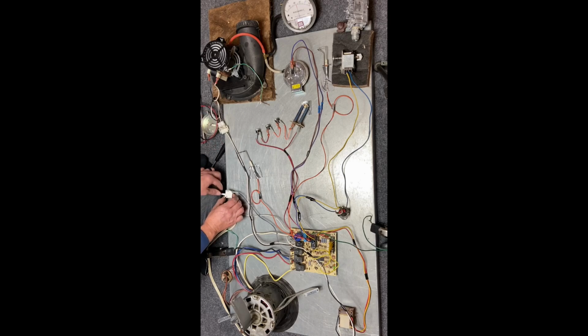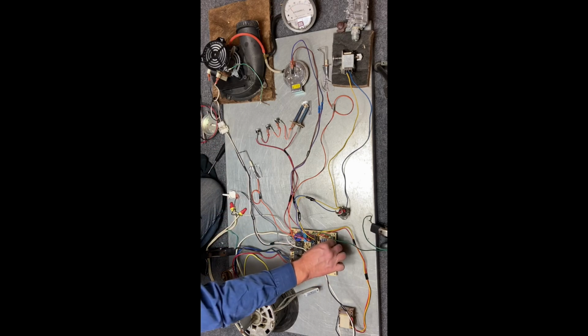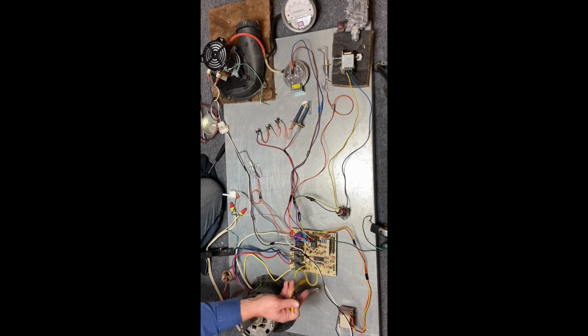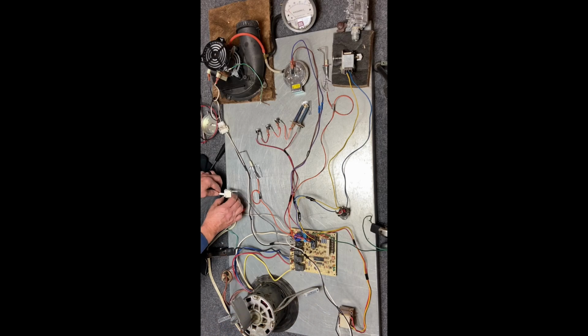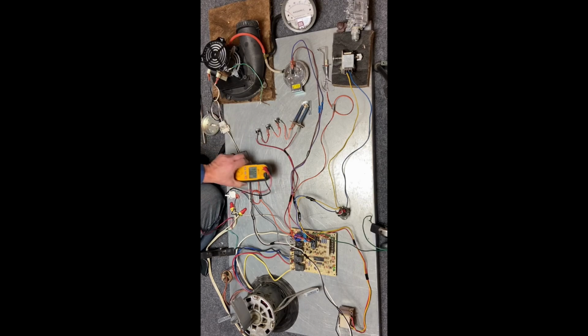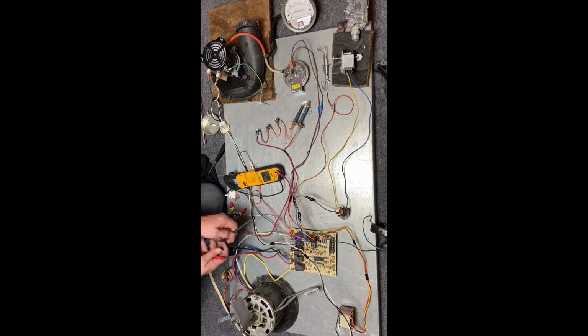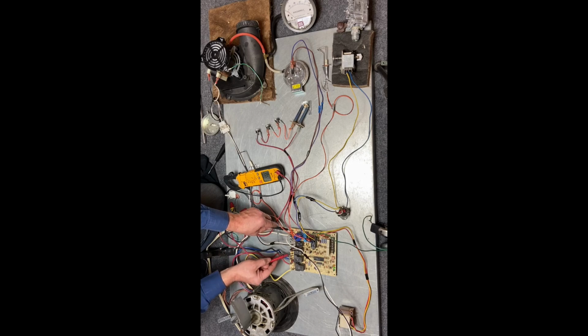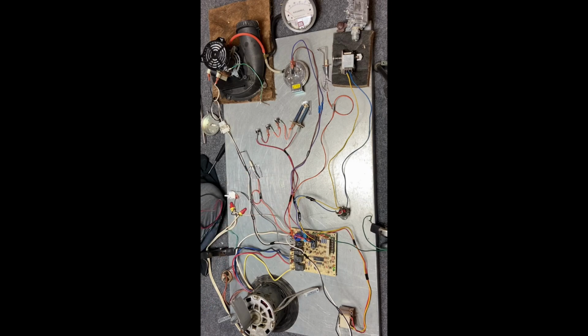So what we're going to do next, I'm going to take the jumper off for our call for heating. So now when I energize my control board, nothing should happen because my thermostat's not doing anything. So I know that I'm getting 120 volts to my board because I can again use my meter. So the bottom number is voltage, and I check between my neutral and my primary, and it shows I'm getting 123 volts to my control board. So what would happen though if one of our limit switches failed? So what I'm going to do is I'm going to manually trip this limit.